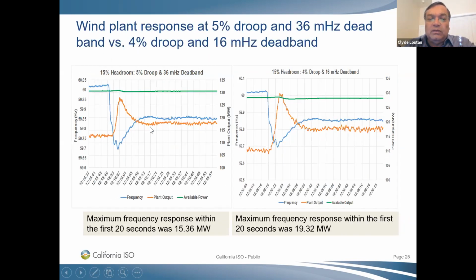Now I'll just jump into frequency control. We wanted to see for a low frequency event, and this green here is really the capability of the plant itself, right? So for a low frequency event, which is this blue, you can see how this plant responded. And this is with the current settings that we have at the ISO, which is a 5% droop and a 36 millihertz deadband. And you can see you were able to get, in 20 seconds, roughly 15 megawatt response for a low frequency event.